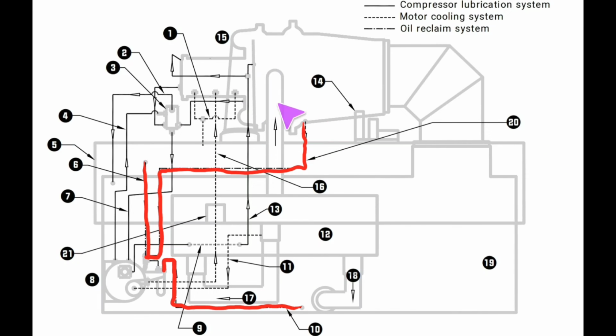And how this happens is basically through the discharge line. Some of the oil is going to get grabbed by the refrigerant stream in the compressor and sent out the discharge. When that happens, the most common points for that oil to be collected are this evaporator assembly and then this suction line. Then, again, they're trying to pull vapor off of the refrigerant, process that oil back out of it, and get it back into the oil sump.